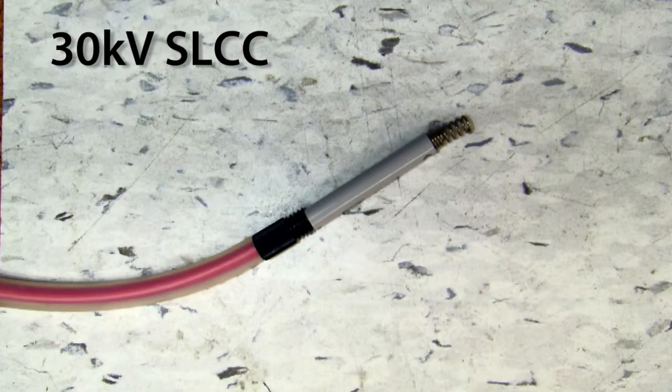The 30kV SLCC comes standard on all Simco-Ion charging bars and applicators. The length of this connector is 2.25 inches. This size connector needs to be used in conjunction with 30kV supplies such as the VCM30 and MCM30. Commonly used charging bars include the PINNER, PINNER-T, and PINNER-LP bars.